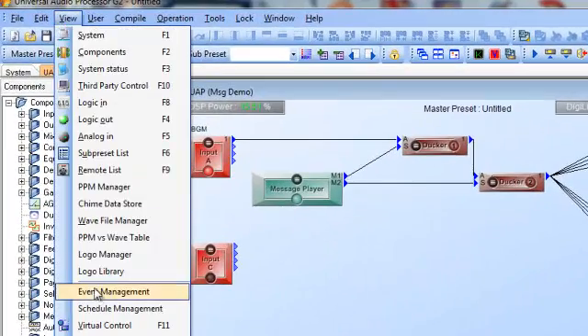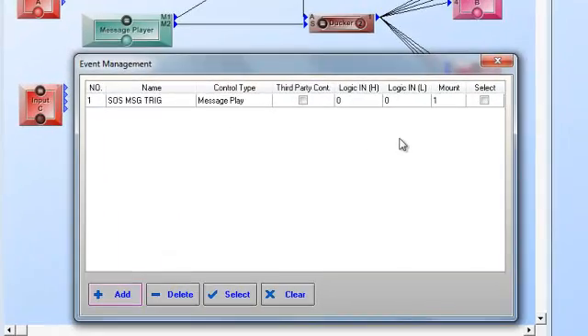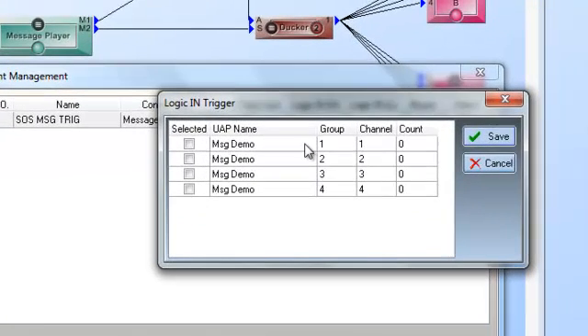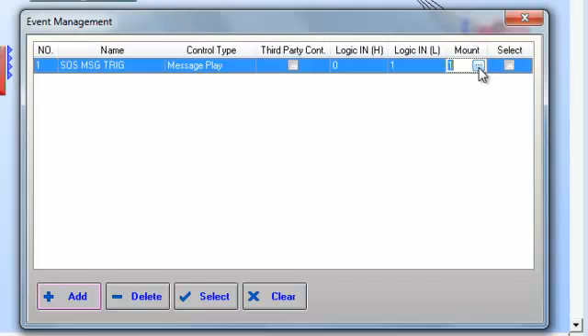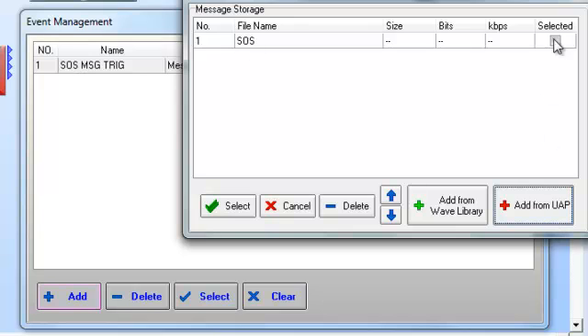If you want 4 TTL logic inputs, make sure they're channels 1 through 4, then the remaining channels can be analog. You can't mix them up because they won't even appear when you set up the event. Let's go to View, then Event Management. I want the SOS message to trigger on logic input channel 1. Because I've configured only the first 4 as logic inputs and 5 through 16 as analog, only those 4 show up here as trigger options. I select channel 1 — now when logic input number 1 goes low, meaning the impedance drops and you get a contact closure, it will play the message.